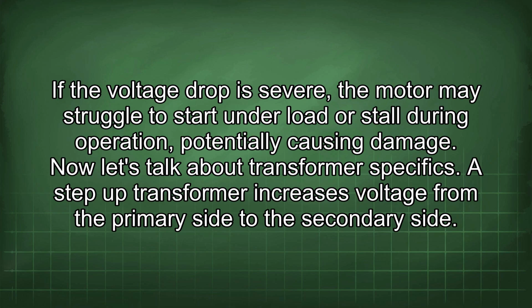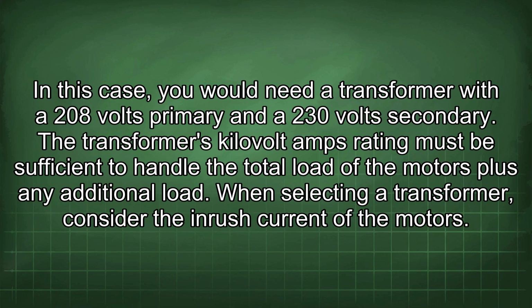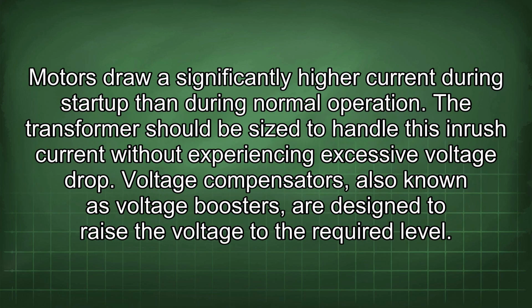Now let's talk about transformer specifics. A step-up transformer increases voltage from the primary side to the secondary side. In this case, you would need a transformer with a 208 volts primary and a 230 volts secondary. The transformer's kilovolt amps rating must be sufficient to handle the total load of the motors plus any additional load. When selecting a transformer, consider the inrush current of the motors. Motors draw a significantly higher current during startup than during normal operation. The transformer should be sized to handle this inrush current without experiencing excessive voltage drop.